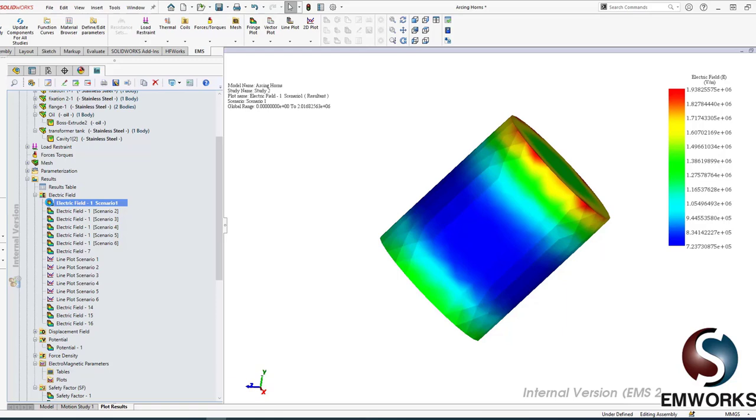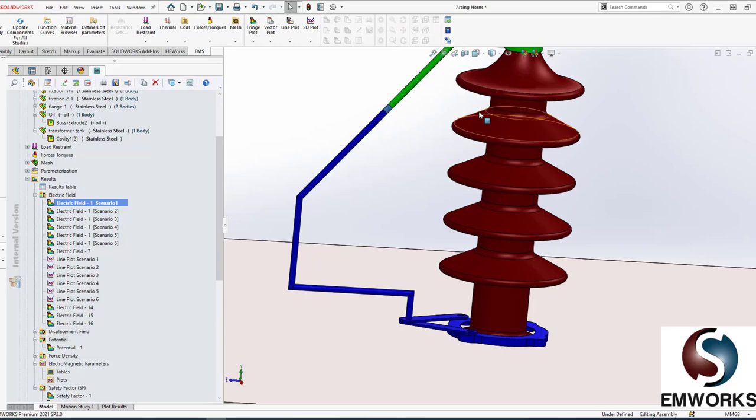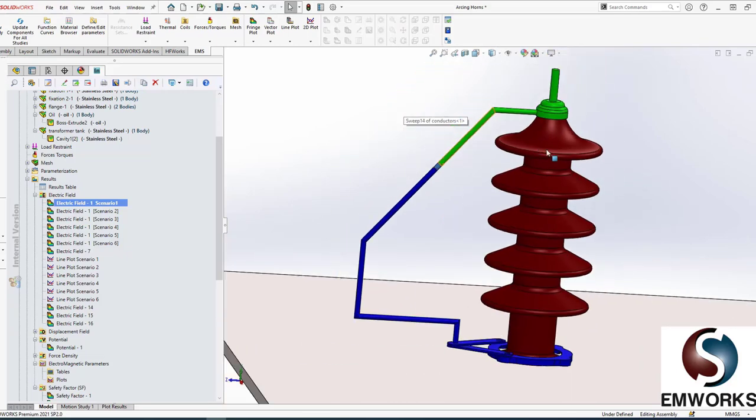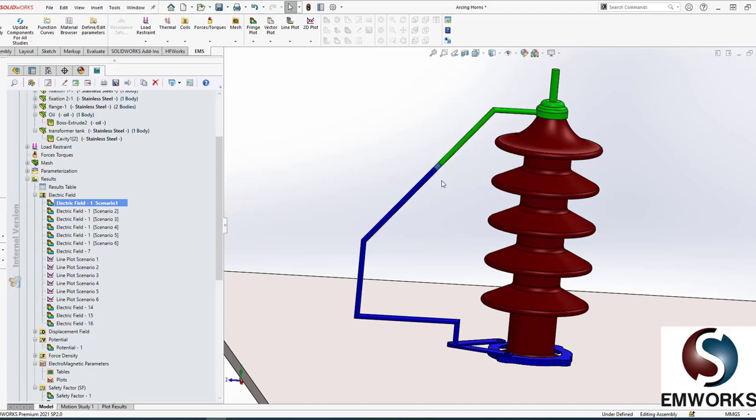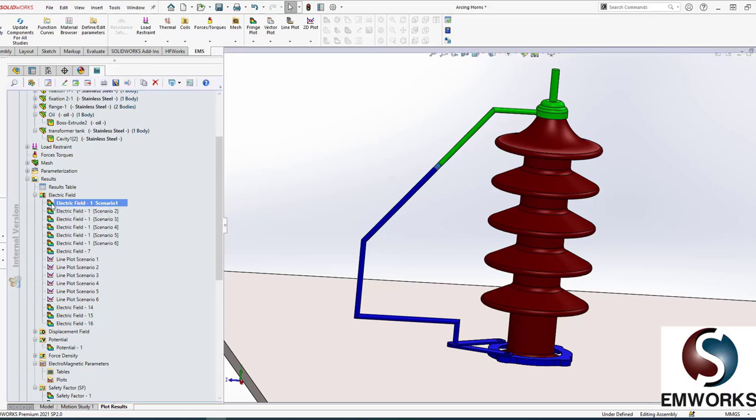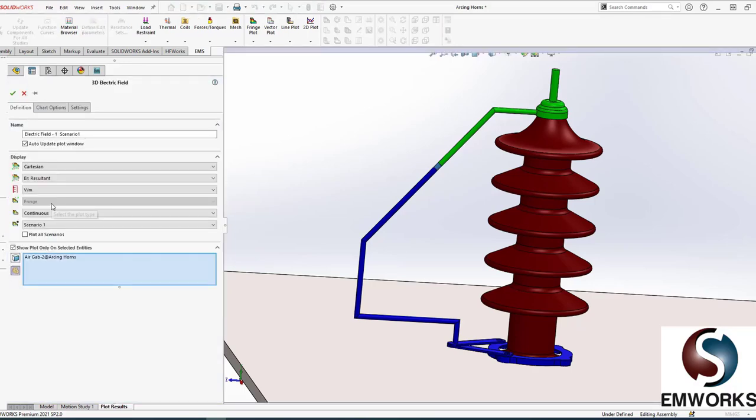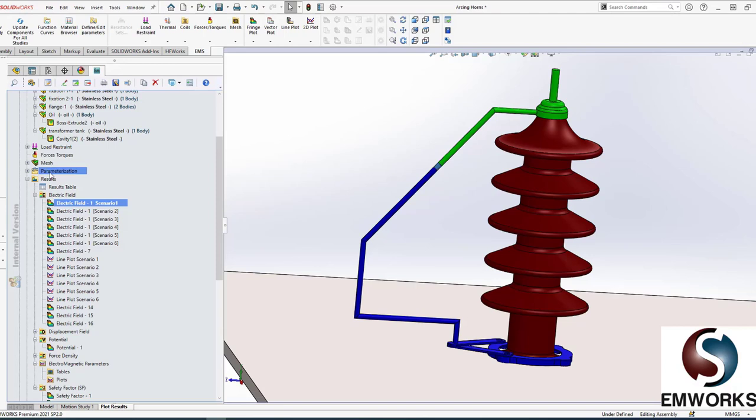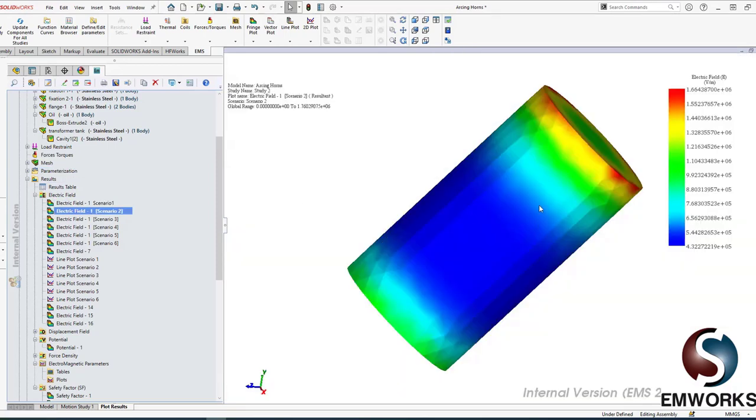Now it's important to design the air gap that will not produce corona while the voltage is the operating voltage, say 10,000 volts. You don't want the normal operating condition to create corona right here; it's going to defeat the whole purpose of this design. You want it to create corona only at the fault or the lightning strike voltage. So scenario one, scenario two in the air gaps—you can see there's no breakdown.